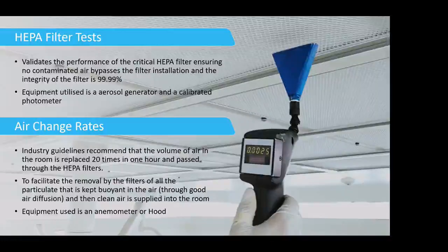So what we do is we introduce a very precisely defined aerosol challenge upstream of the filter, and we measure the concentration of aerosol upstream. We then scan the downstream, the other side of the filter, and we measure the percentage of these oil droplets that have made it through the filter, and then it's a fairly straightforward sum. If we've got 100% saturated air behind the filter and 0.001% is making it through, then we've got our filter classification. So that's always done when you fit a new filter, and it's done pretty well periodically every 6 months to a year, just to give reassurance that the facility is still functioning.